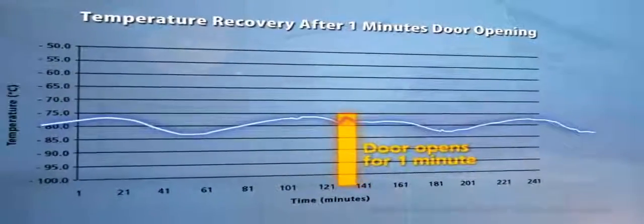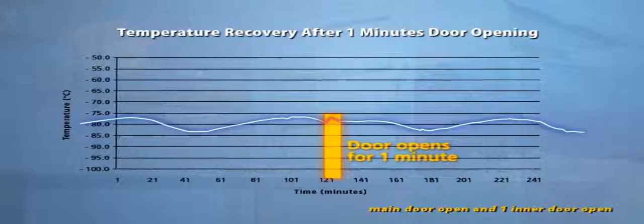Recovery time after door opening is the time required for the temperature to recover after the user places samples back to the freezer. Esco ULT freezer can achieve 4 minutes recovery time following a 1 minute door opening.